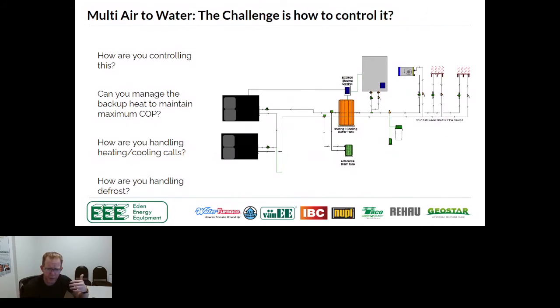This again is a multi-unit setup, so you need to be very, very careful with a multi-unit setup. Make sure you've got adequate flow through these units. Whether you do reverse return or do a short fat header, I don't care how you pipe it. With a multi-unit hydronic heat pump, be very, very cautious of how much flow you need to have through those units. The number one thing that gets us is multi-unit applications where they're not quite set up properly and we start to run into problems. So I always say heat pumps are not boilers.